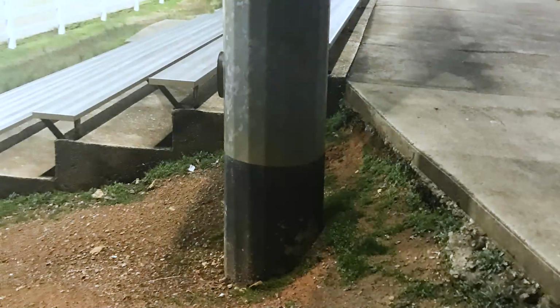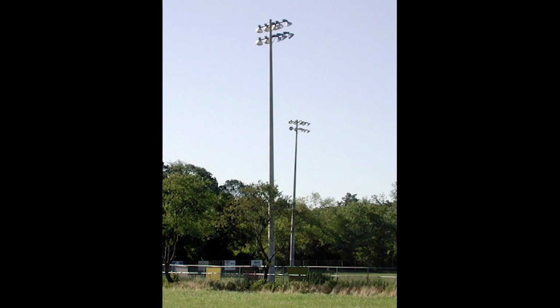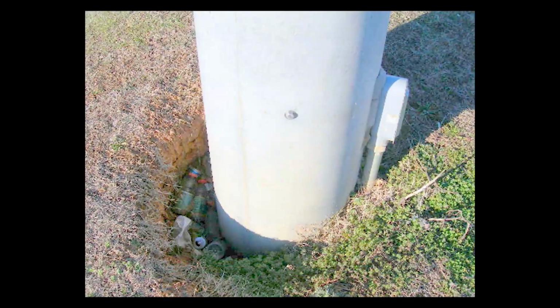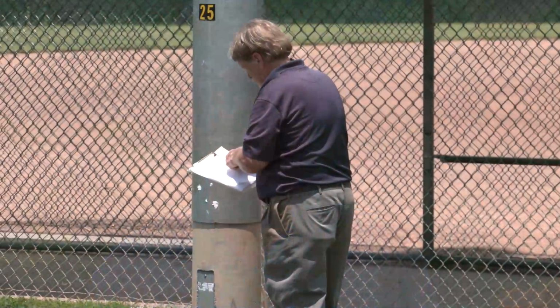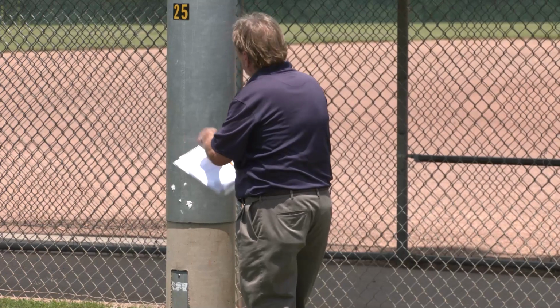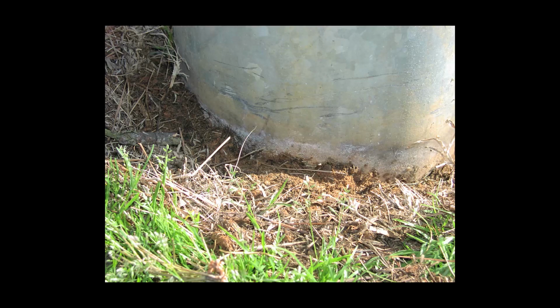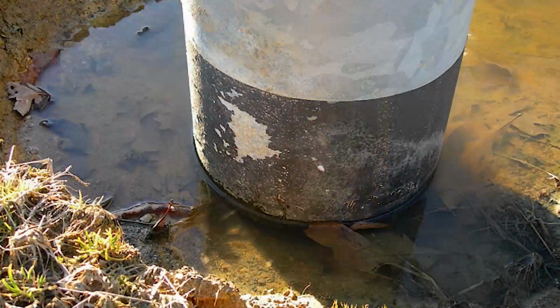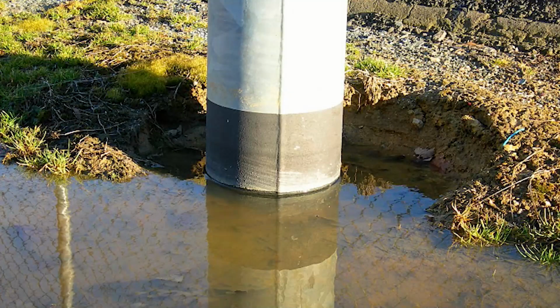And while concrete and steel poles installed beneath grade with properly designed foundations shouldn't have any issues with leaning or twisting, some facilities have poles that have been buried directly into the ground without a properly designed foundation. So as with wood poles, you want to check for signs of misalignment of your poles. In addition to visually inspecting everything on your poles above grade, it's critical to check what's happening below grade. Another major problem that can occur at the base of direct buried steel poles is corrosion from groundwater tables that can raise the level of moisture on the exterior and on the interior of the pole.